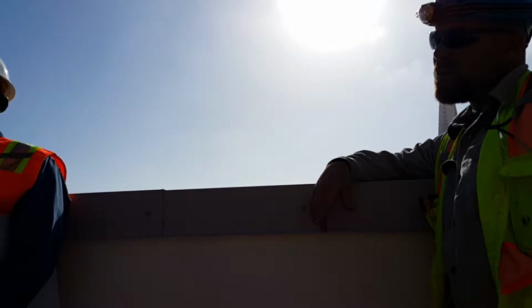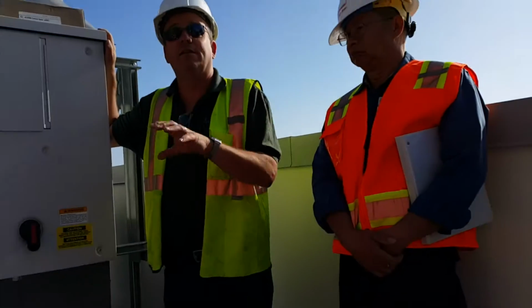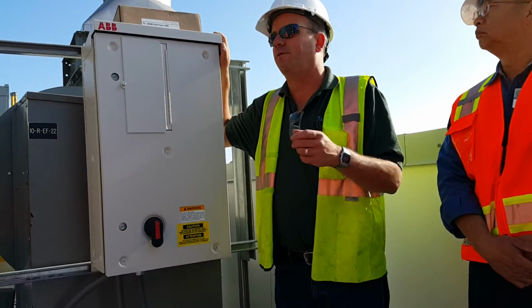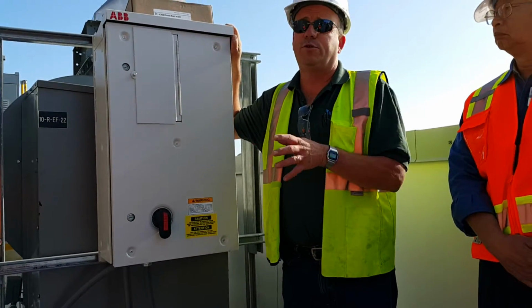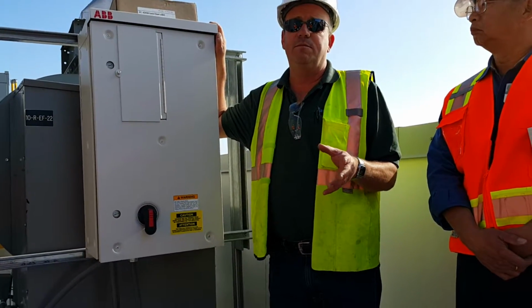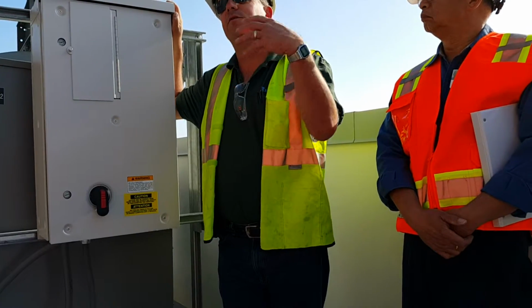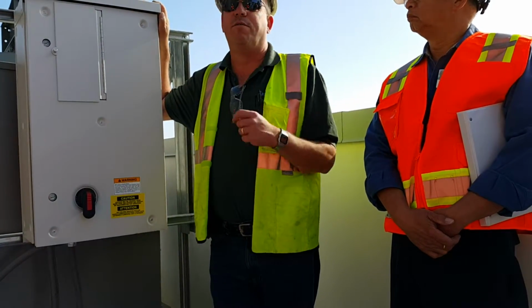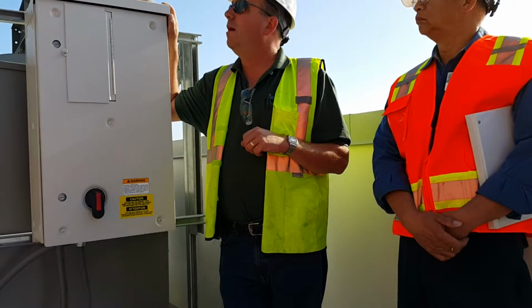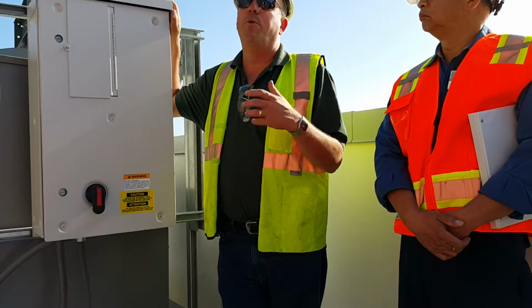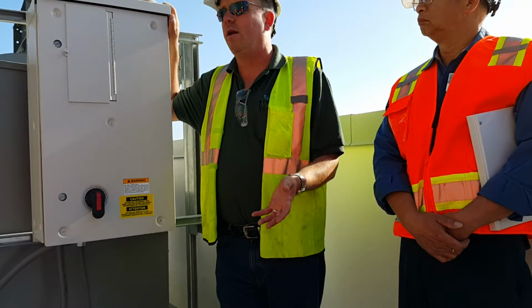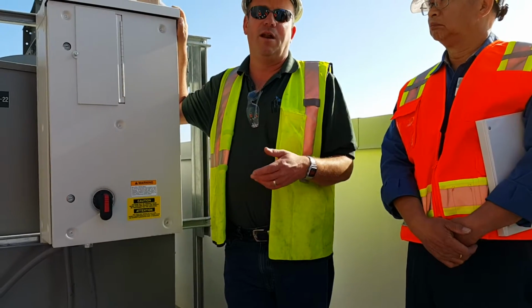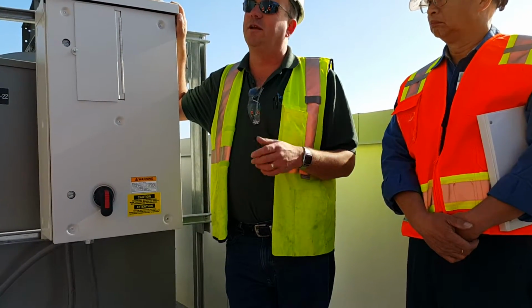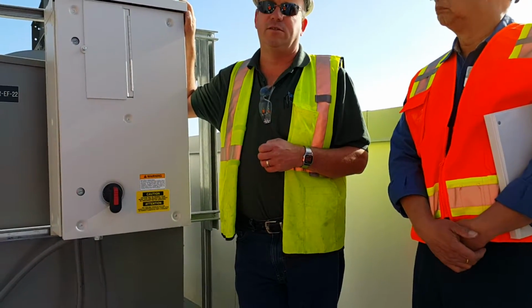If you measure ohms, it basically is a dead short, pretty close to it. And all of a sudden it tries to line start, tries to send everything through that motor. The drives will trip out. Compared to drives from earlier days, which would blow the first time, as soon as you did that, boom. But these have inductors on the output, so they will survive it. They'll trip on overcurrent. Still not a good idea to do it a lot. If you keep doing it, I'm sure it's going to break down the output transistors.